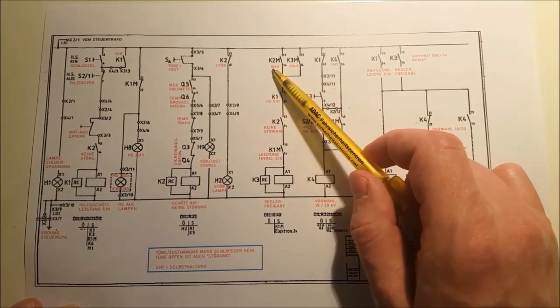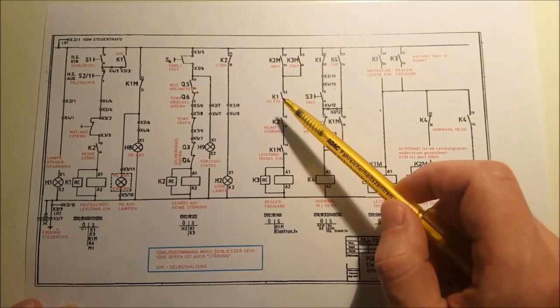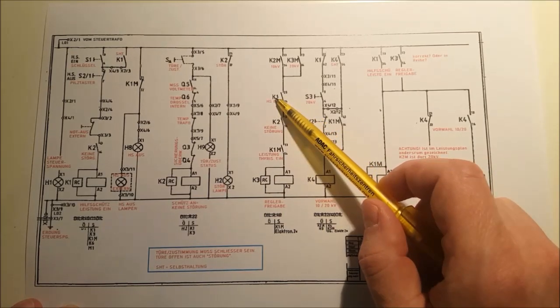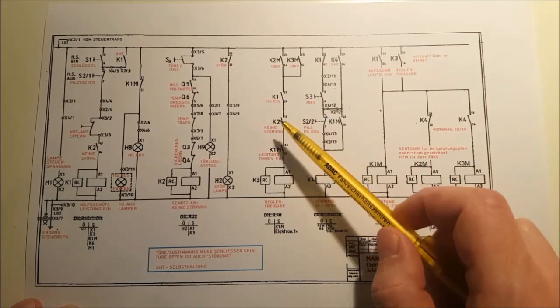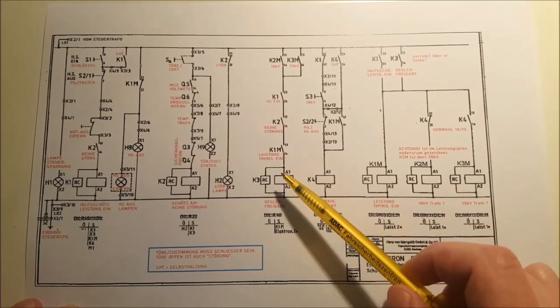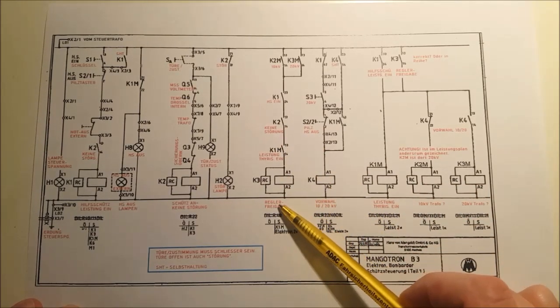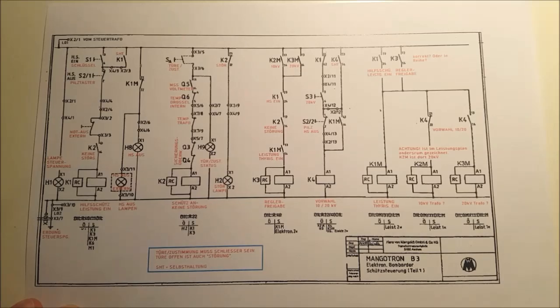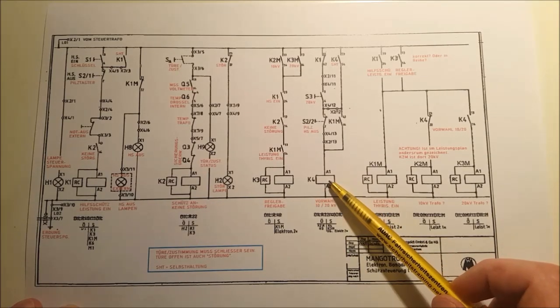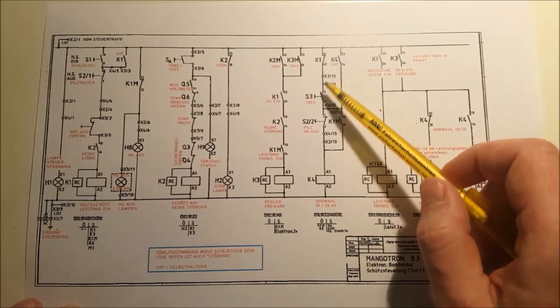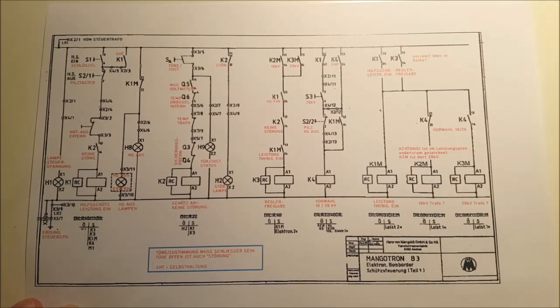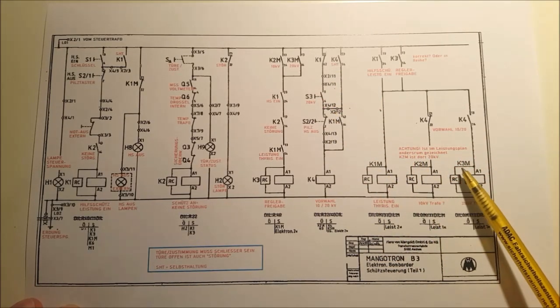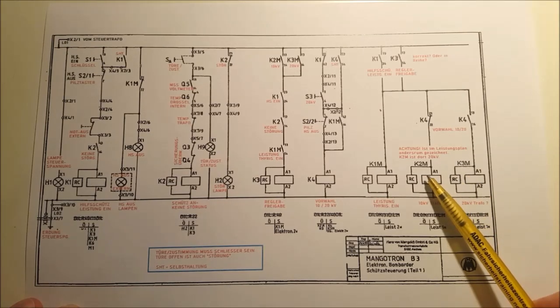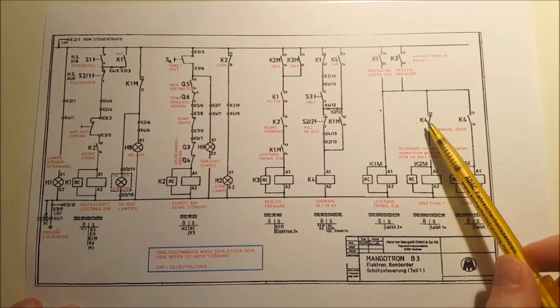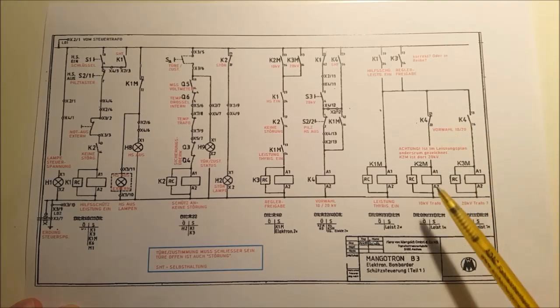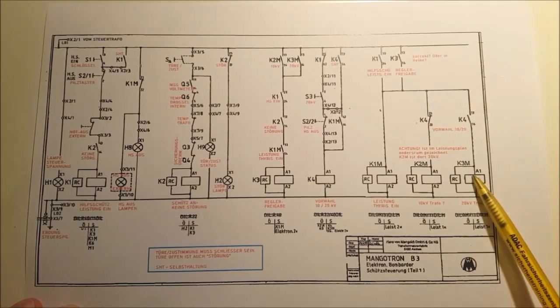When we have either 10 kV or 20 kV mode selected and the auxiliary contactor is on and we have no error and the main power contactor is on, then this contactor gives the enable signal to the thyristor controller. Then K4 is the contactor that selects between the 10 and 20 kV mode, and then here these contactors switch the transformer primaries to either 10 or 20 kV mode, and they are interlocked by these contacts of K4, so it's either this one or that one.